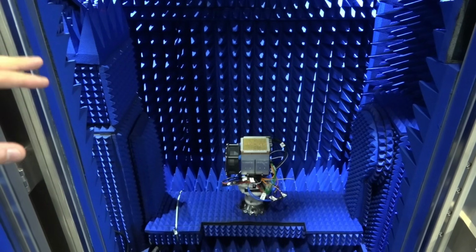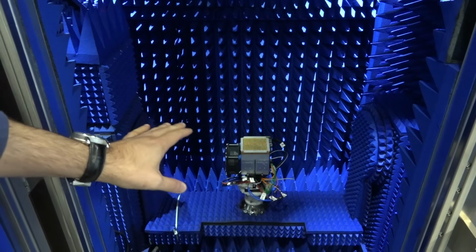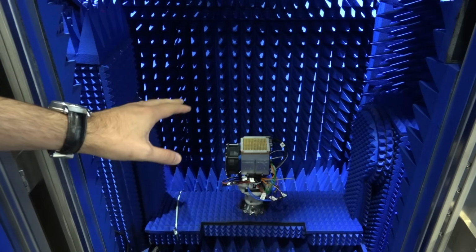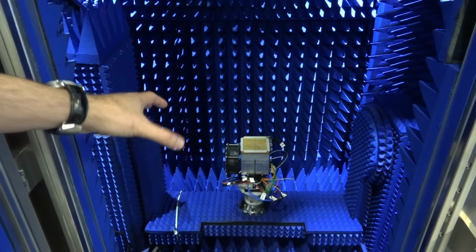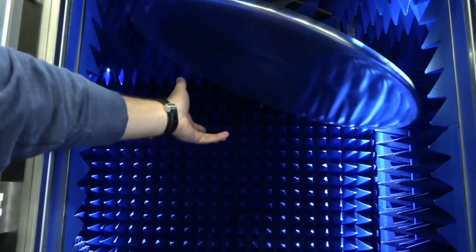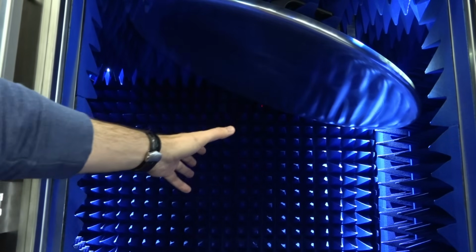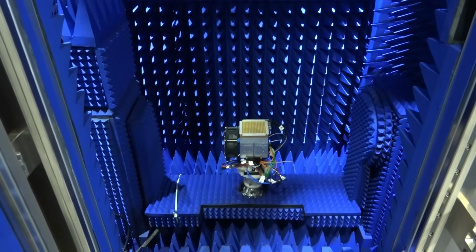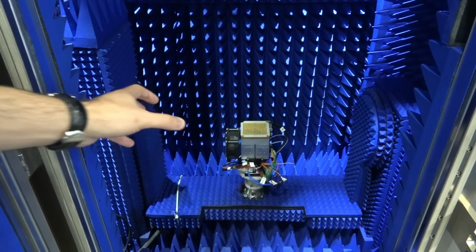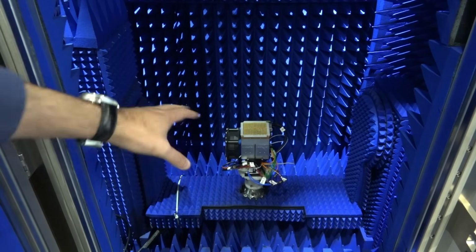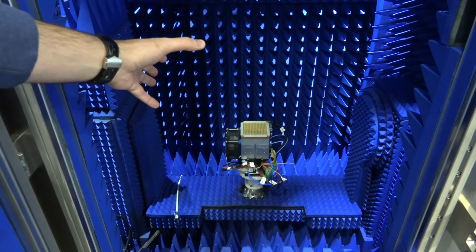So in this system, you're able to bring your measurement plane to the edge of your device. And that's because you can calibrate the entire system. Here at the very top, you can see that we have our near field, far field lens translator over there. So you're really measuring this thing essentially in equivalent far field. We have a PNAX on the other side, which I will show you. You can do all your calibration, bring the measurement, and then get complete characterization of the device.